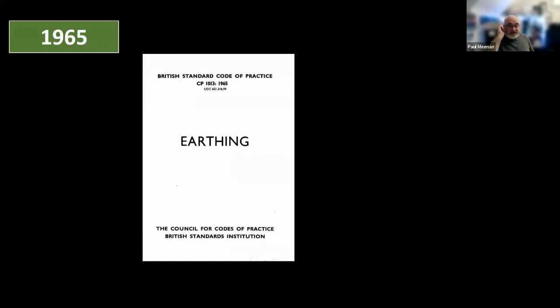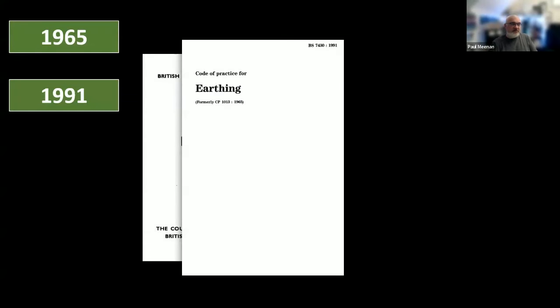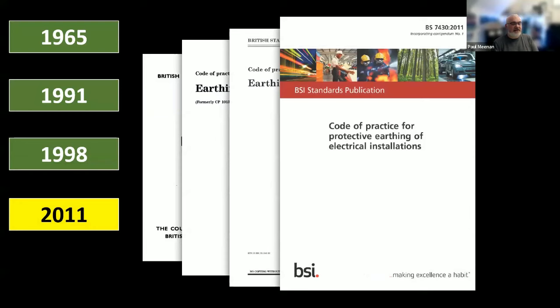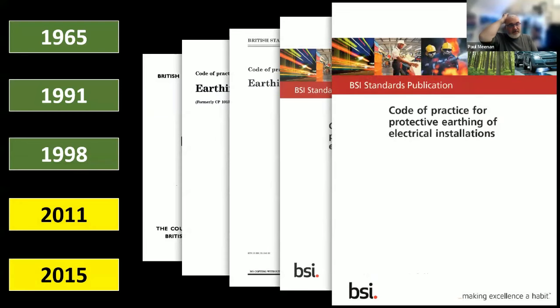So getting onto the earthing standards now, huge journey. As I said, 1939 was the first protective device that relied on earthing and talked about earthing. But the actual earthing standards themselves, in 1965, CP 1013 was published by the Council for Codes of Practice, or the British Standards Institution. That was then updated and renumbered to BS 7430, which is, anyone in Europe, you mention BS 7430, they'll know what you're talking about. Well, the first edition of that after the 1965 one was 1991. And then in 98, it was completely rewritten. 2011, again, updated into the modern format, and we're currently working off Amendment 1 of 2015. So that's where we go to for a lot of our fundamental nitty-gritty earthing and bonding details.